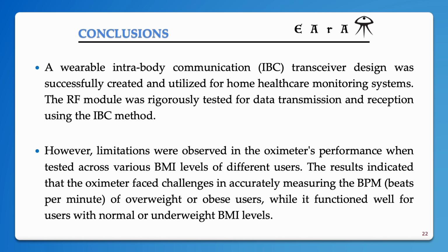Limitations were observed on the oximeter performance when tested across various BMI levels of different users. The result indicated that the oximeter faces challenges in accurately measuring the BPM, beats per minute, of overweight or obese users, while it functions well for users with normal and underweight BMI levels. Maybe for a future experiment, we need to see why this occurs. From my point of view, maybe it is because of the fat or the thickness of the skin that reduces, maybe, the attenuation or the losses of the signal.